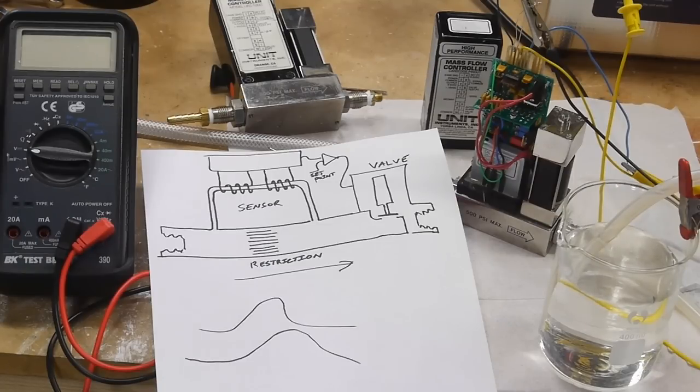This actually makes sense since earlier I said that pressure will cause the rotameter to be incorrect and in this case a higher pressure means a lower volume flow so the rotameter will read low when the pressure is above its intended calibration point.